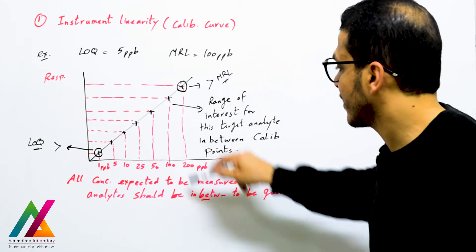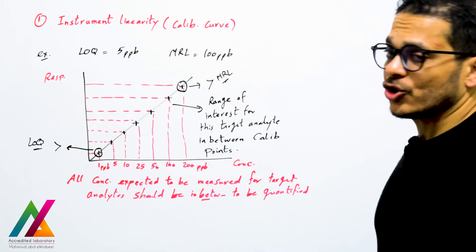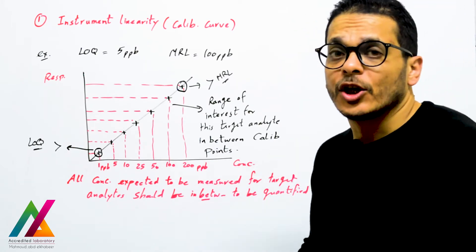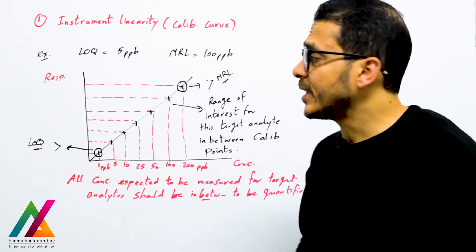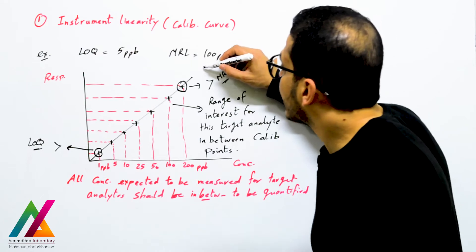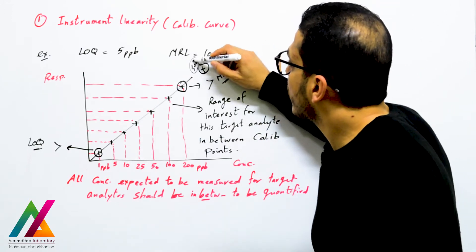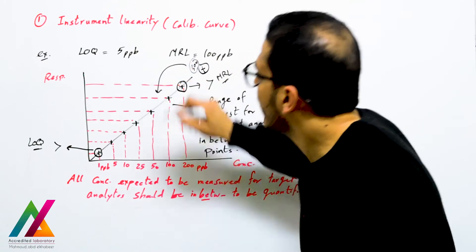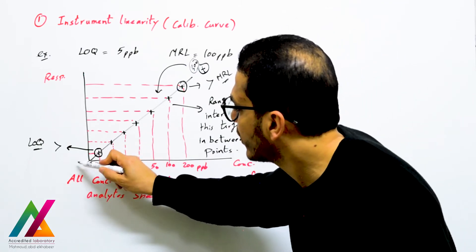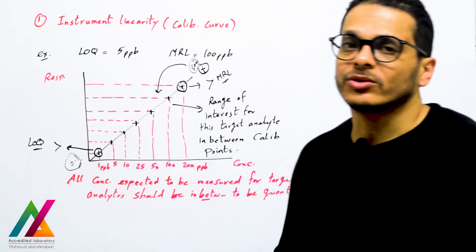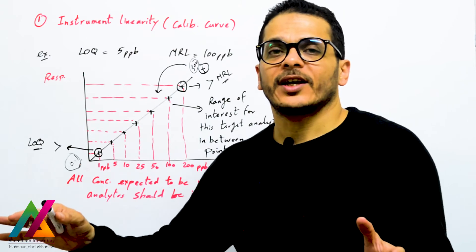All concentrations expected to be measured for this target analyte should be between your calibration points for high accuracy quantification. If you get a result higher than the last calibration point — for example 300 ppb — you must dilute the sample so the result falls within calibration range. If a result is below the first calibration point, such as 0.1 ppb, it will be reported as not detected.